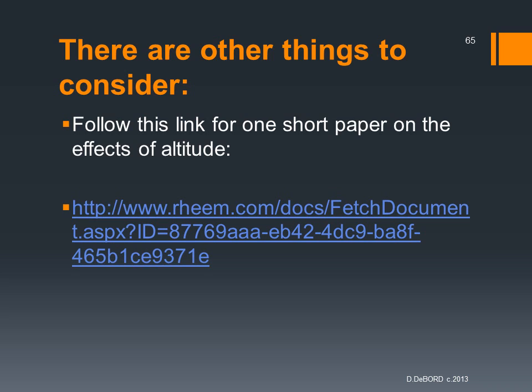In the era of the Sears Tower and Empire State, etc., those are around 100 stories, maybe 1,600 feet, but now we're going higher. Plus, you're not at sea level, so it's having an effect. But if you have a Burj Khalifa or one of those super tall buildings, your gas considerations are different at the top of the building than they are at the bottom of the building. Also, the temperature is different and other conditions.